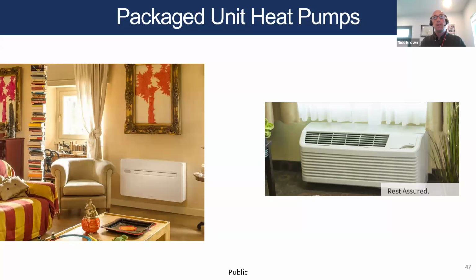That said, usually the ducts and your old HVAC system have been vastly oversized for the load. It's always a good idea to get your HVAC company to do a load calculation of your house, especially if you're modifying the envelope and giving it a deep energy retrofit, because you'll find you need much less tonnage than is currently installed in almost every case. HVAC contractors tend to install far too large HVAC systems for fear of getting called back.